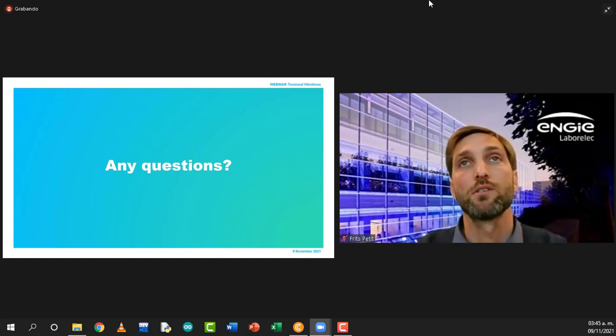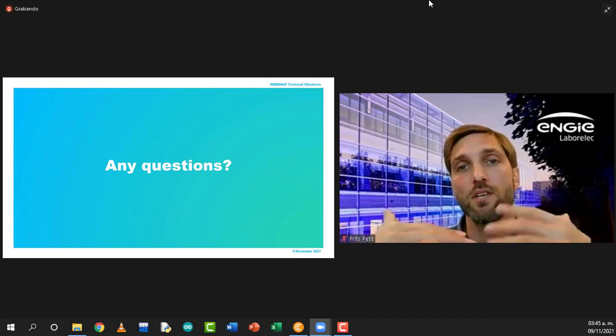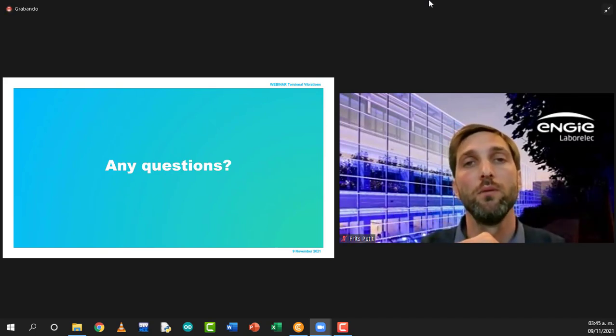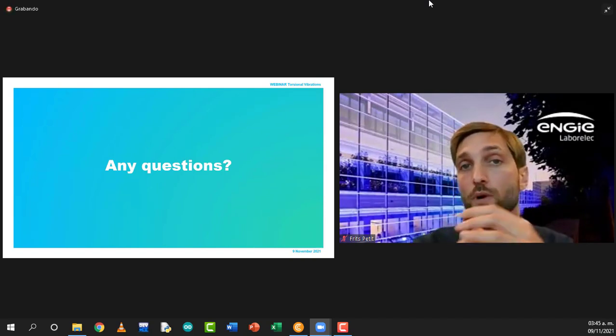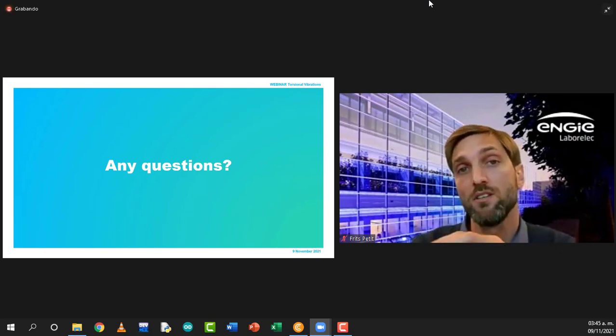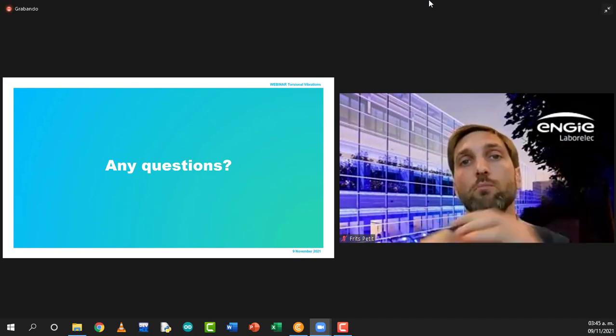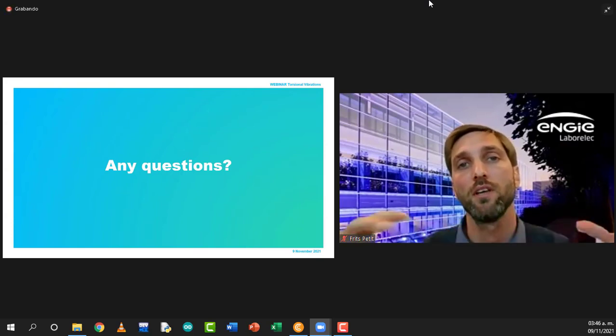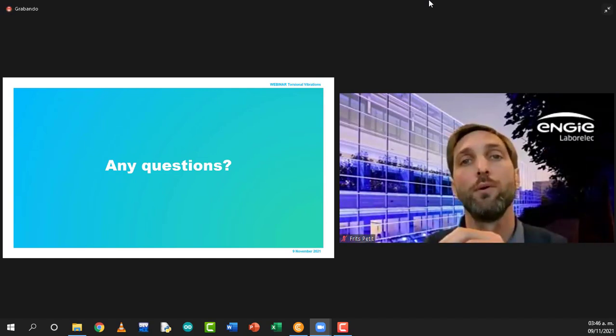Yeah, that's a good question, because typically we're not able to put a sensor everywhere we want. As already mentioned, in 90% of the cases, we're able to reuse the existing sensors. So this means that the existing sensors are typically well positioned. In some rare cases, unfortunately, it's not the case. And then we base ourselves on the theoretical model of the shaft line, so the deformation. If you think again about the 18 Hertz deformation, the gas turbine twisting against the generator, there the shaft end would be a very good location for detecting that mode.